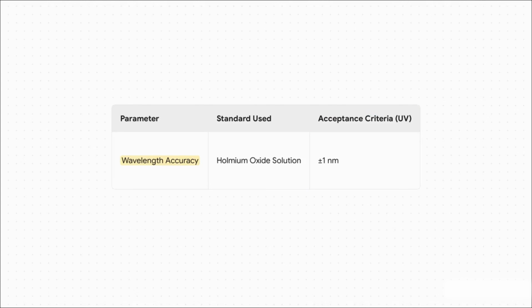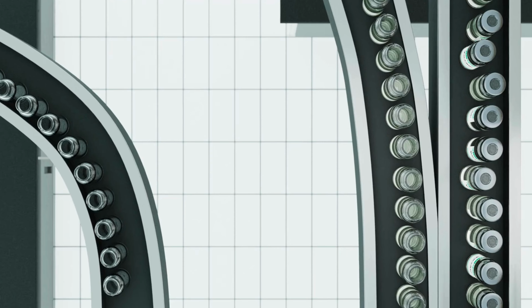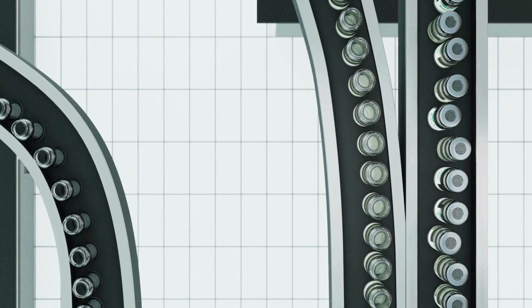First up is wavelength accuracy. We use a certified standard, like a holmium oxide solution, to check if the machine is seeing the correct wavelengths of light. Basically, we're making sure the instrument isn't colorblind, because if it is, it could totally misidentify a drug. And look at that acceptance criteria. It can't be off by more than 1 single nanometer. That is incredibly precise.